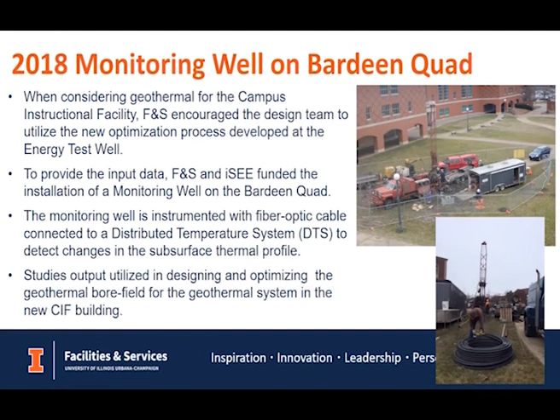That happened in 2019, the campus instruction facility, or as we call it, CIF. The geothermal system here will supply approximately 135 tons of heating and cooling capacity, about 65% of the total building demand. Our estimated reduction in GHG emissions is about 70% compared to a similar size building. The system was also designed to enable expansion and to achieve LEED Gold.